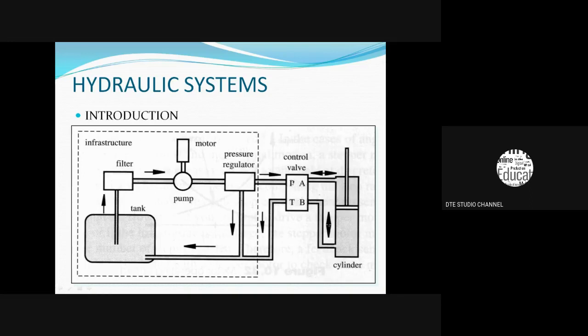In the case of direction control valve, whenever the controlling element is activated, like a push button or hand lever, P communicates with A in one position. That is, fluid enters one end of a cylinder and the piston moves downwards. In the same stroke, the fluid present in the bottom end of a cylinder returns into the reservoir from B to T. Whenever P communicates with A, in the same stroke, B communicates with T.